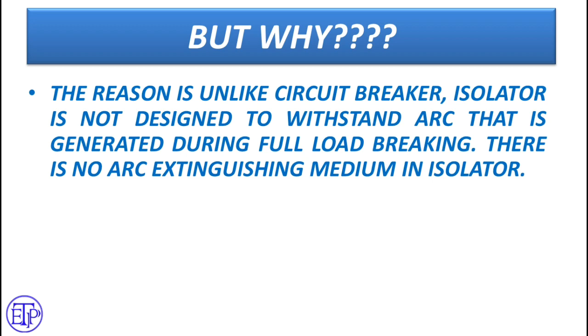Why such limitations? Because, unlike a circuit breaker, an isolator is not designed to withstand the arc that is generated during full-load breaking. Whenever you are breaking a load current — a huge amount of current — or there is a significant voltage difference between two terminals after breaking, it will create an arc. This isolator contact does not have the capability to withstand or extinguish that arc. It doesn't have any arc extinguishing media.